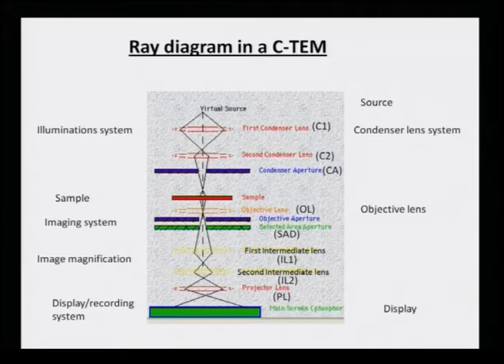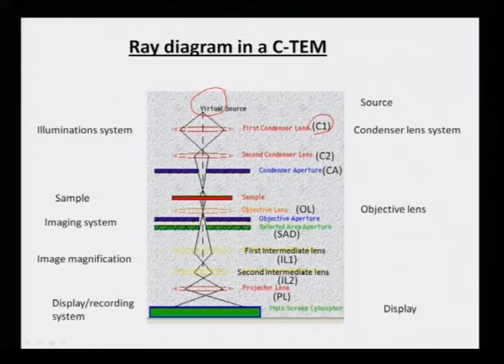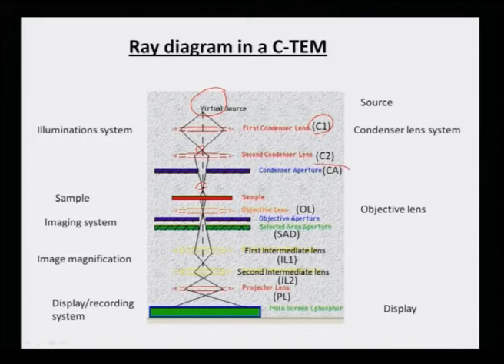The TEM looks exactly similar, except there are more complicated lens systems and the source is an electron beam rather than optical light. In a simple ray diagram: there is a source — which can be an electron source — the electron beams are focused by a first condenser lens to a very small focused beam, and that focused beam can be defocused and re-focused by a second condenser lens onto the sample. Apertures such as the condenser aperture are used to control the beam size.